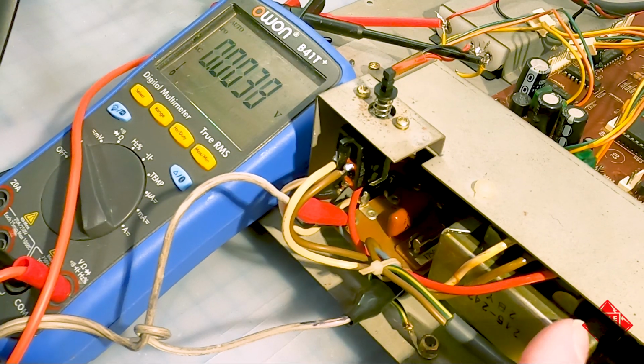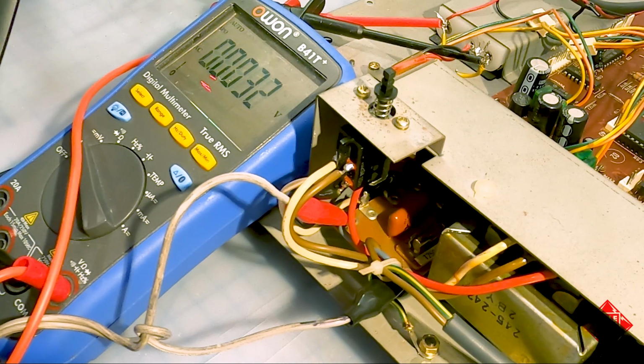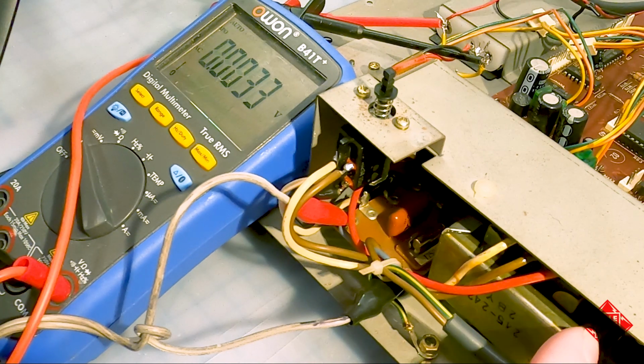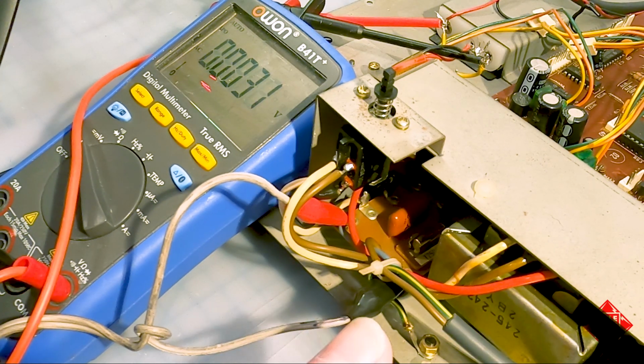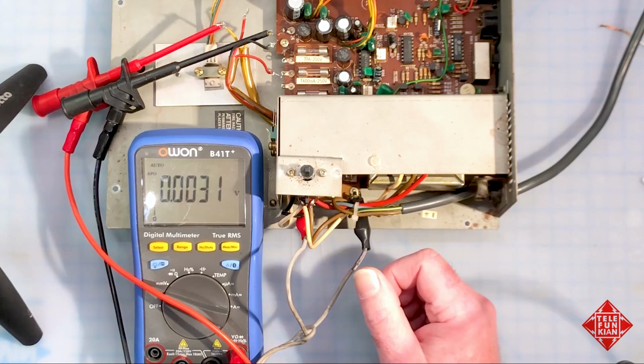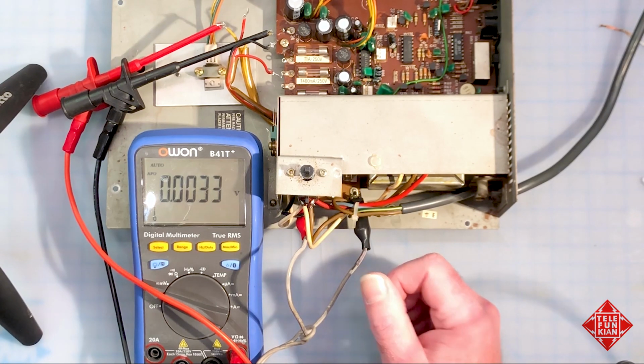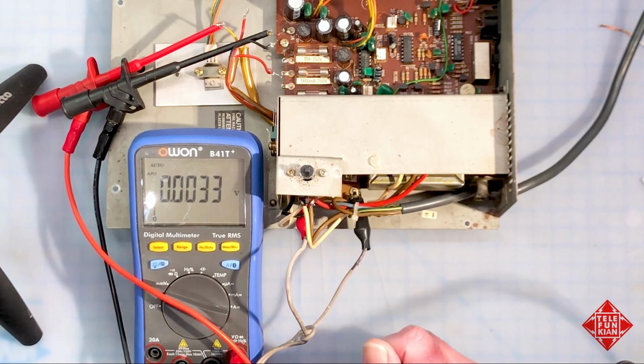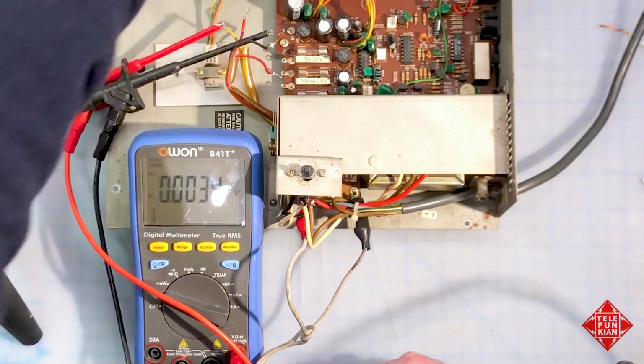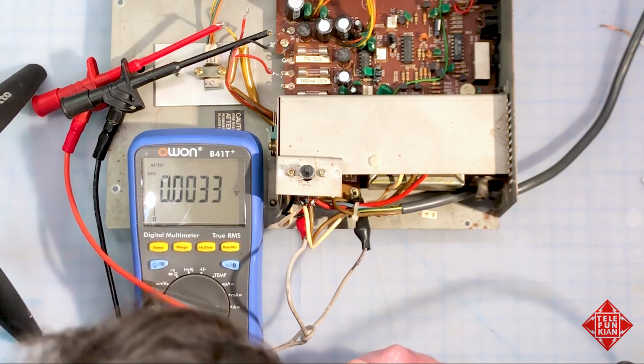Indeed, I have an R-core transformer on order from overseas that I'll be installing into the instrument as part of the conversion to the 120 volt standard here. So what do we do in the meantime? Yeah, this is another failure, but there could be more, and hopefully our damaged 5 volt winding hasn't taken out some of the components on the CPU board that rely on that 5 volt supply.